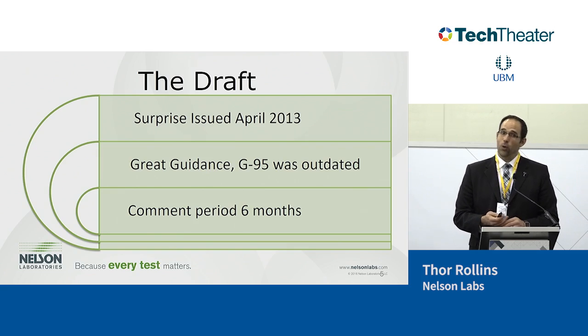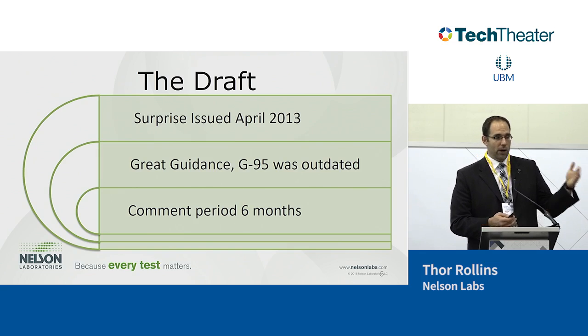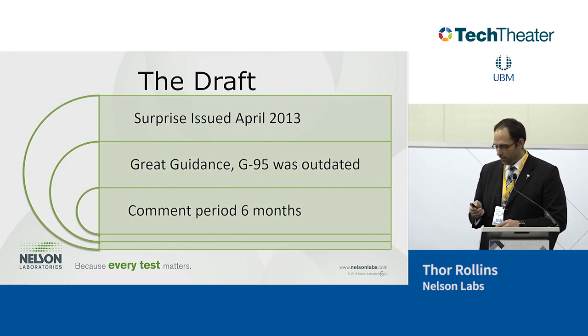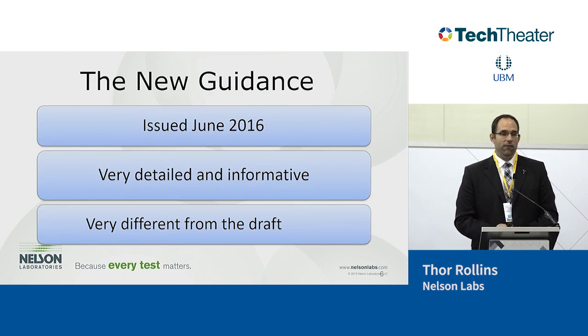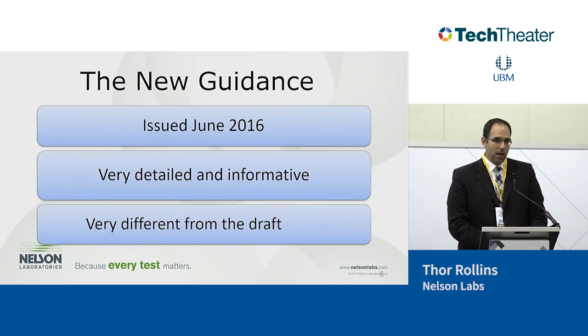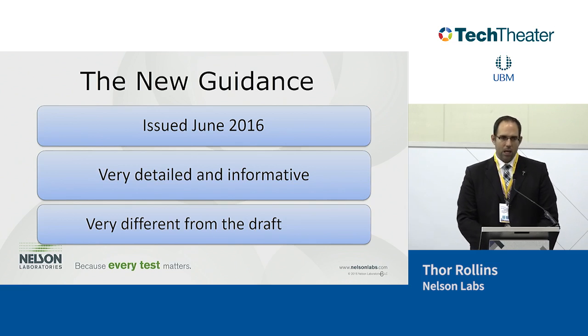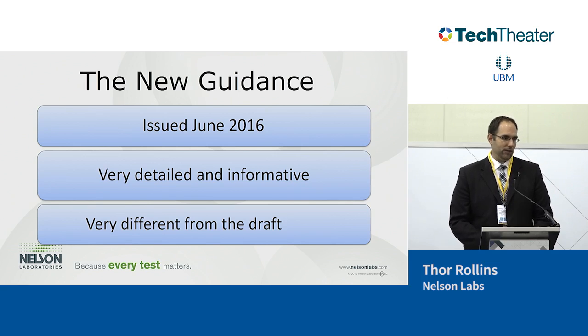Because of that, it took quite a long time for them to go from the draft phase to a final document. The final document was released in June of this year, and then became effective in September of this year. This draft actually is a very good product. I think it's very useful for medical device manufacturers, and it's longer than the other drafts, so it could take a little bit more time and coffee to get through. But I would recommend getting through this draft because it really does give you insights into what the FDA is thinking as far as biocompatibility.